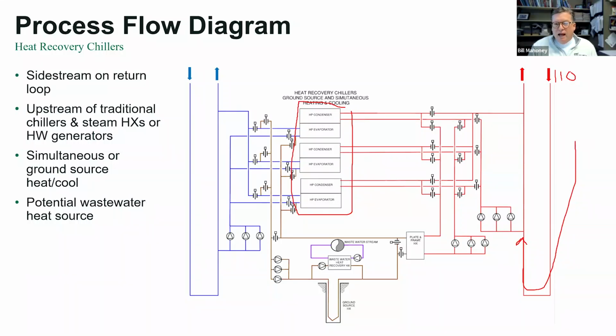And so we allow those pieces of equipment, which have a harder time reaching the higher supply temperatures, to see the coldest water and do what they can. It's a side stream arrangement, so it draws off what it can. We get as much energy out of this as the heat recovery will let us do, and that can be limited sometimes. As I said, we only have so many bores, so we can only get so much heat out of it. We also might be limited by how much simultaneous cooling we're doing if we're not going into the ground at that time. So there's a number of reasons why it's a good idea to just have this side stream, and it just adds heat to the flow as it goes by.